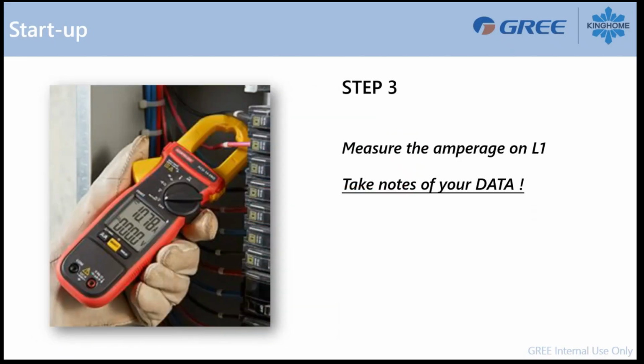Make sure you also take the amperage on your L1 power line, from the electric panel, or if you have a disconnect switch, or any breakers already installed in the air handler. Take the amperage of your fan motor and take the amperage of the electric strip. Take notes of your data. It is always recommended to leave a checklist just beside the air handler when you have done your startup. You will have around 20 amp per 5 kilowatt for a 5 kilowatt duct heater, so 20 amp per 5 kilowatt plus the air handler blower.